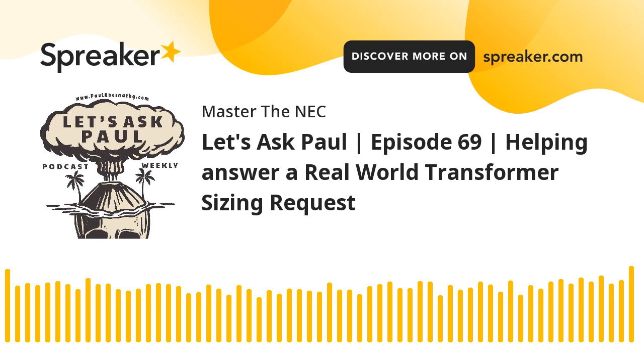Now, the next thing we're going to say is, well, the maximum overcurrent protection is 100 amperes. So that's the size or the rating of the breaker that's going to be in our disconnect, which is also going to provide our overcurrent protection for this HVAC unit. So we've got that protection. Right now we have a 100 amp disconnect, and we have 4 gauge copper from that down to the unit. We're good. Now, kicking it back to our secondary conductor sizing for those secondaries.